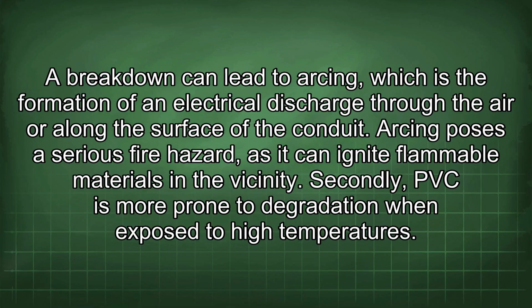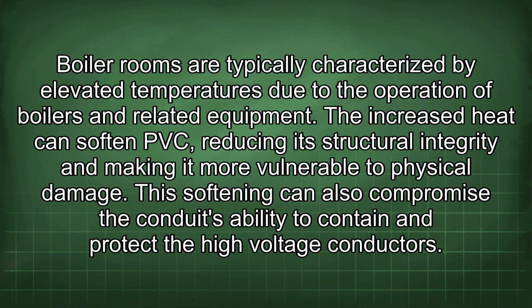Secondly, PVC is more prone to degradation when exposed to high temperatures. Boiler rooms are typically characterized by elevated temperatures due to the operation of boilers and related equipment. The increased heat can soften PVC, reduce its structural integrity, and make it more vulnerable to physical damage. This softening can also compromise the conduit's ability to contain and protect the high-voltage conductors.